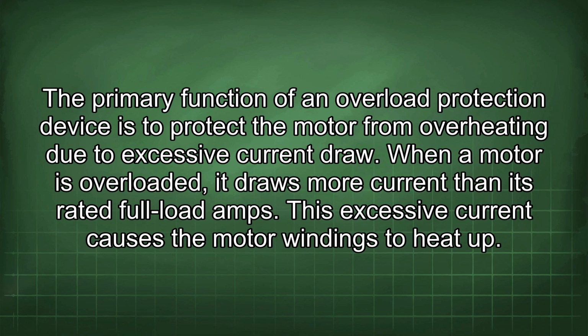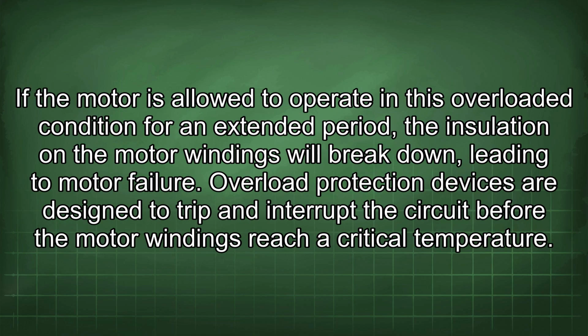The primary function of an overload protection device is to protect the motor from overheating due to excessive current draw. When a motor is overloaded, it draws more current than its rated full load amps. This excessive current causes the motor windings to heat up. If the motor is allowed to operate in this overloaded condition for an extended period, the insulation on the motor windings will break down, leading to motor failure.